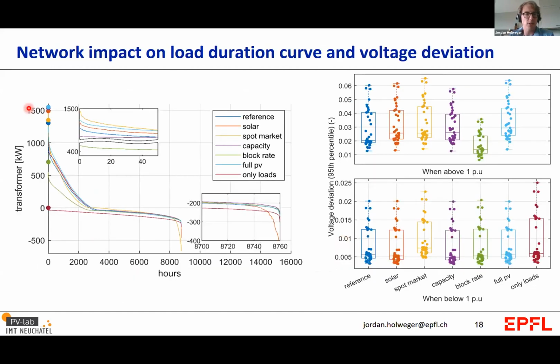Let's have a look at the network impact on the load duration curve. This is the power transformer and the number of power along the year, and also the voltage deviation. We split it between when you have a voltage that is above 1 per unit, meaning you have a local excess of energy, and when it's below 1 per unit, meaning a local deficit of energy.